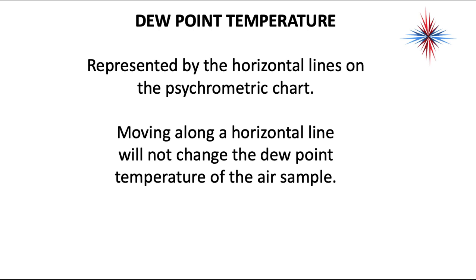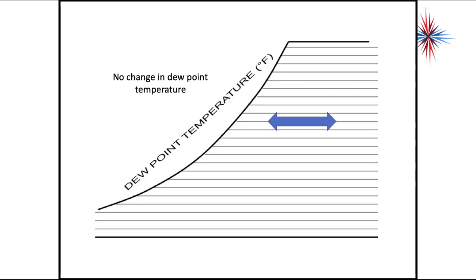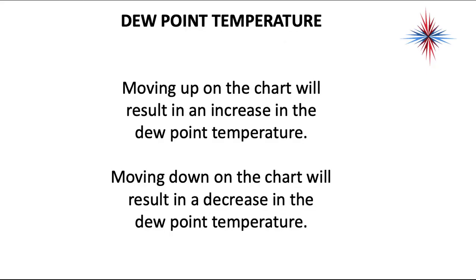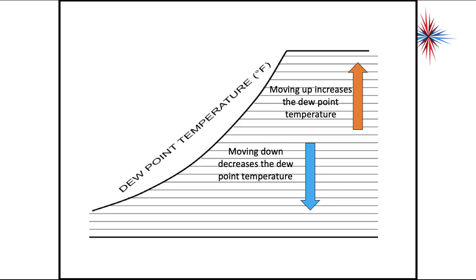Dew point temperature is also represented by the horizontal lines on the psychrometric chart — the same horizontal lines as moisture content. It is also known as saturation temperature sometimes. Moving along a horizontal line will not change the dew point temperature. Moving up on the chart increases the dew point temperature, and moving down decreases it. Going straight across left to right does not change anything.